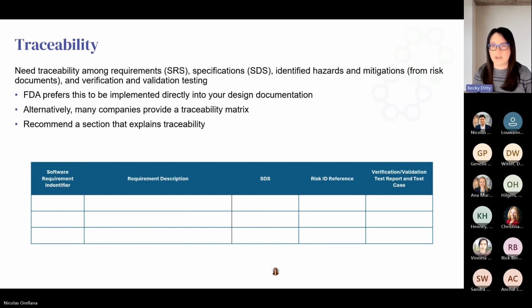I think it's still, as you're working on your design, a good way, especially if you don't have automated systems to help you to track traceability. However, FDA now prefers to see traceability within your documentation itself. And so in your SDS, after various sections, you may have a line item that says this section applies to these specific requirements, and have that throughout your SDS. And in your test reports and your test protocols, for each test case, you identify in that test case which requirements that test case is verifying. In your risk document, when you have mitigation measures, you should trace specifically to the SRS that serves as that mitigation, and then also trace to the test that verifies that mitigation has been implemented appropriately.